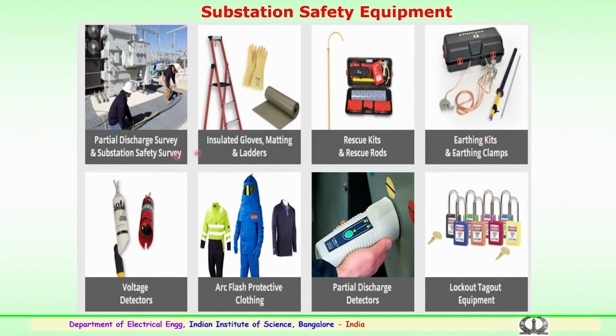It could be partial discharge safety survey equipment where discharges from the substation equipment - it could be a transformer, bus bars, circuit breakers, or any equipment where discharge could be happening. Such measurements in a substation about the activity are a very important aspect to take necessary cautions about exposure by the personnel working in the substation.